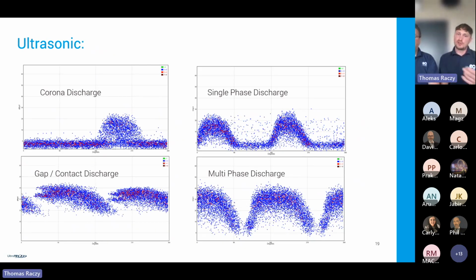Okay, so we discussed internal discharges, and now we move on to ultrasonic discharges. So, discharges on the surface outside of the insulation detected with an ultrasonic sensor. Again, looking at those different patterns, we've got corona discharge, just one electrode, therefore just one grouping. So bottom left corner, we've got gap and contact discharge.